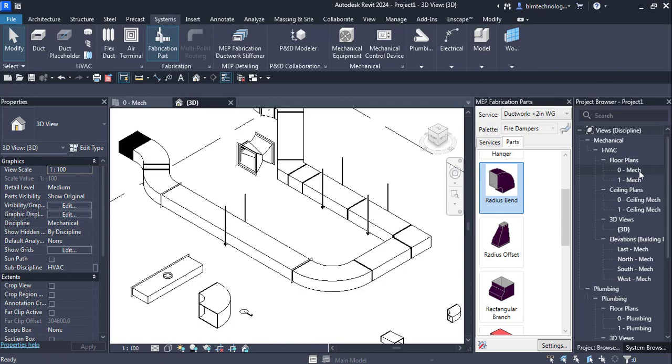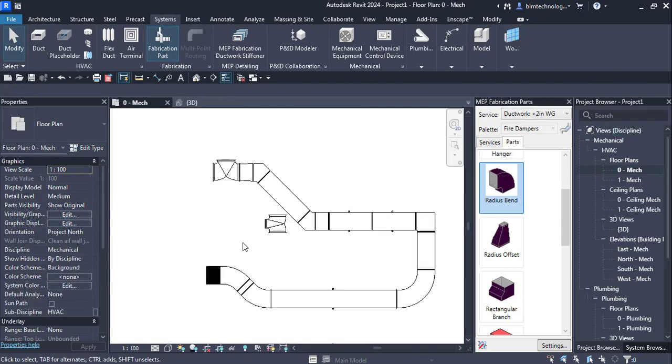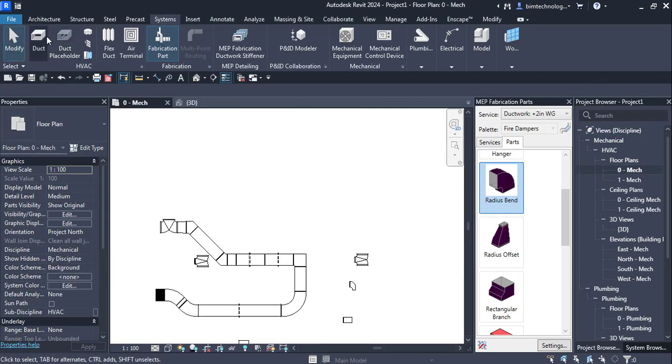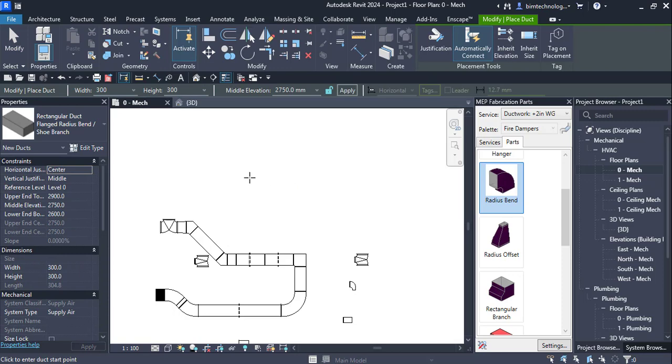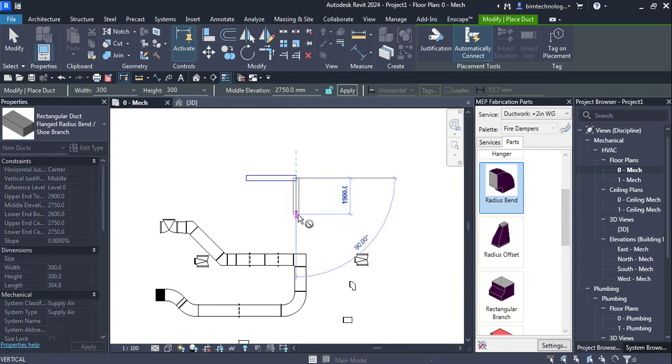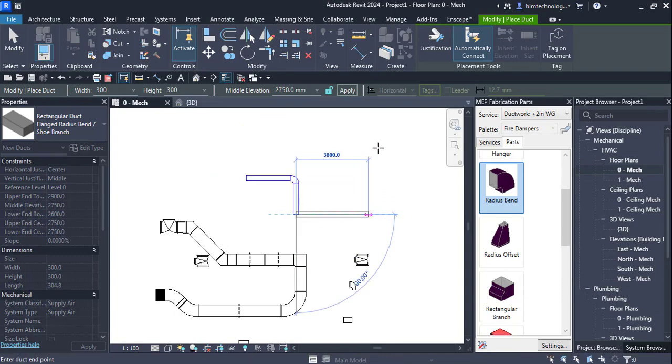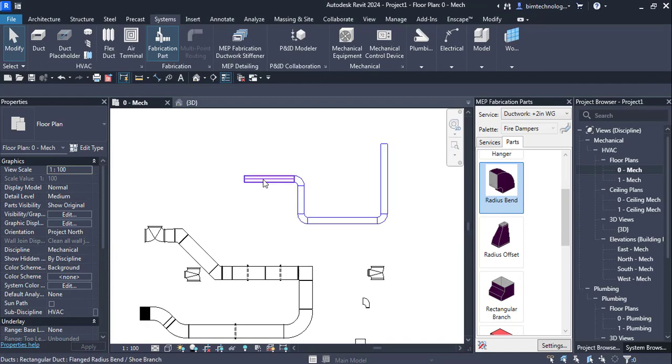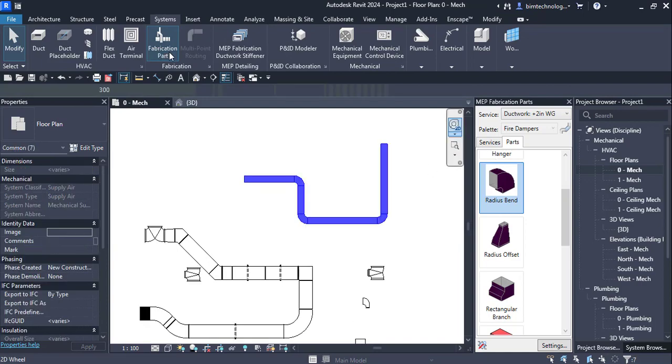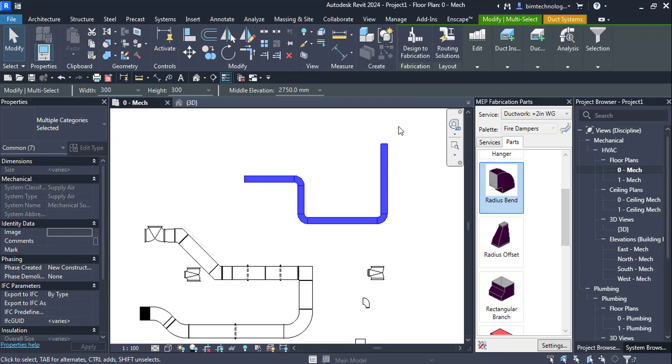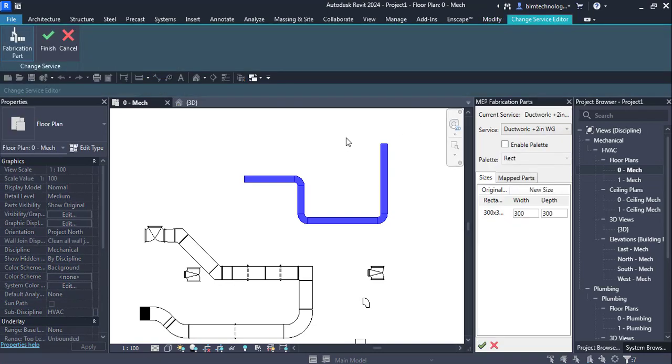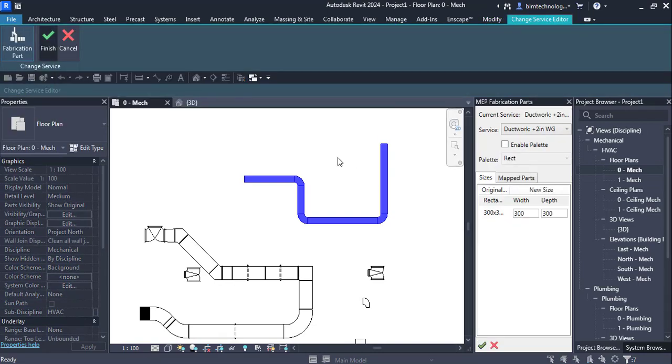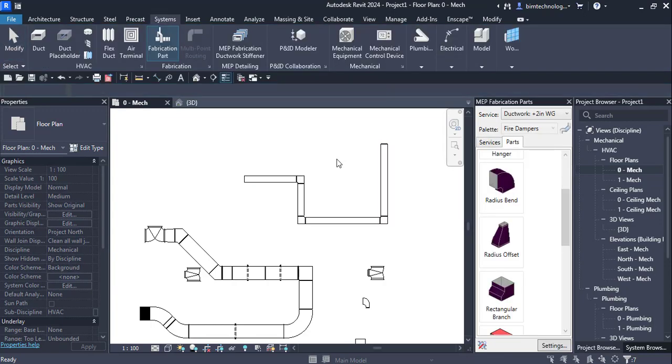And the last thing is that if you have a design of a duct, you can convert them into fabrication. Let's say I have this entire design of the duct that I am creating currently. If I want to convert them into fabrication I select one of them, press the tab key, and then I have this fabrication option over here design to fabrication. And the entire model will be converted into fabrication.